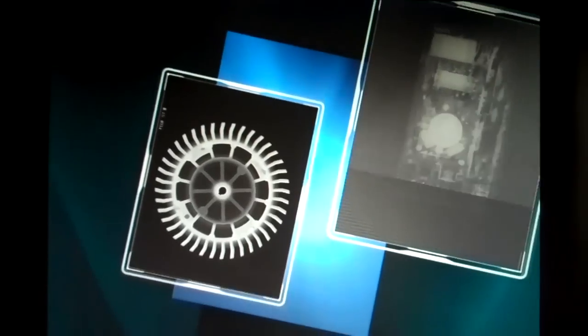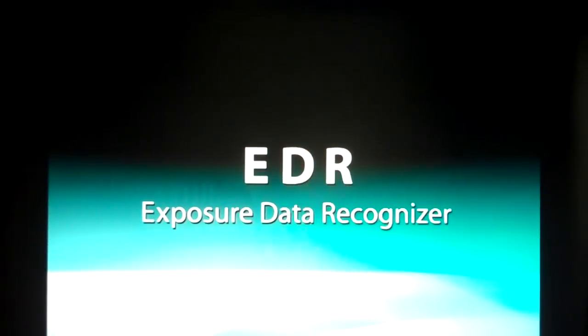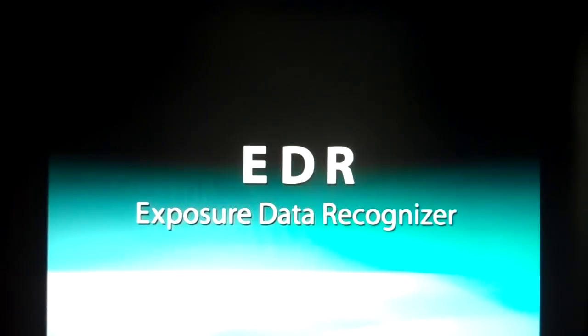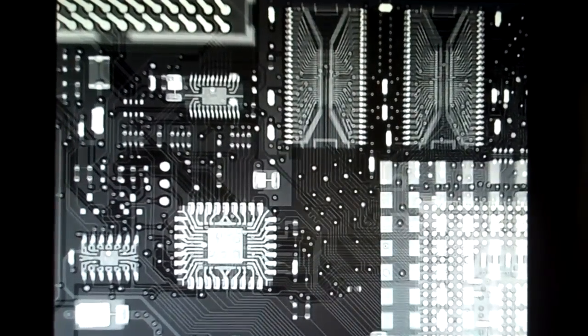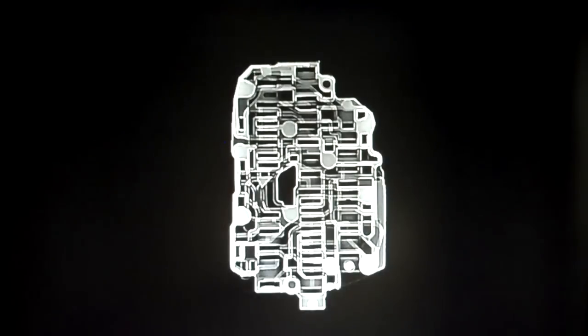Our competitive edge is in the use of the exposure data recognizer, called EDR, on the Dynamix HR. EDR is an exclusive Fujifilm imaging technology and was born as a result of our experience as the world leader in the field of imaging. As we all know, radiography images are aimed at inspection and must have an appropriate level of density and contrast. Generally, all systems require an experienced radiographer to obtain optimum results. However, EDR's automatic density and contrast adjustment functions enable you to confirm the image quality more easily and quickly.